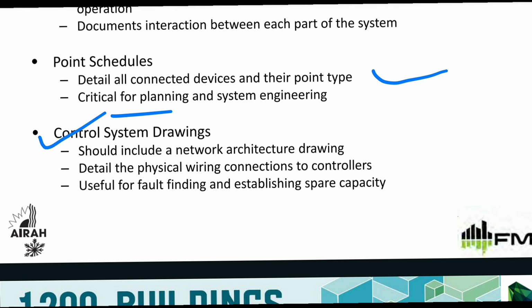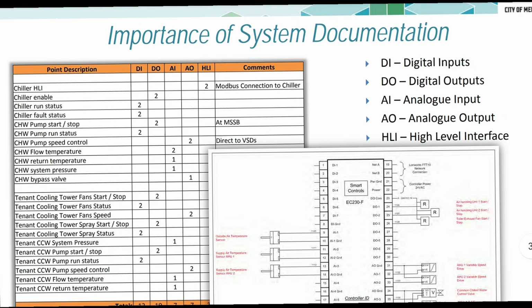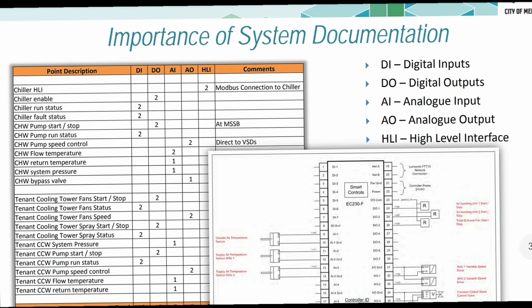Next, control system drawings should include a network architecture drawing detailing the physical wiring connections to controllers. Useful for fault finding and for establishing spare capacity. Important system documentation: DI digital input, DO digital output, AI analog input, AO analog output, HLI high level interface.